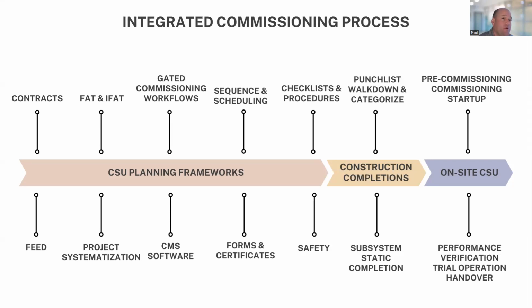Some systems will require even more detailed design review, like control and protection systems or process control narratives. Those need to be reviewed quite frequently to make sure commissioning and operations input go into those processes, so we can actually commission and operate the systems at the end of the project rather than getting a bunch of HMI screens or processes that aren't useful to us.